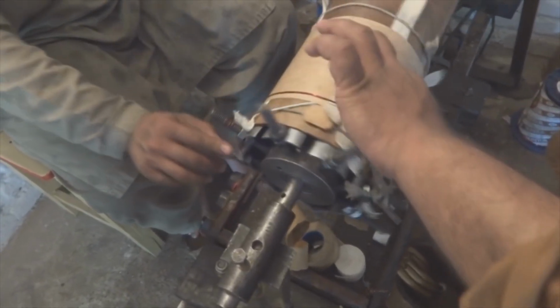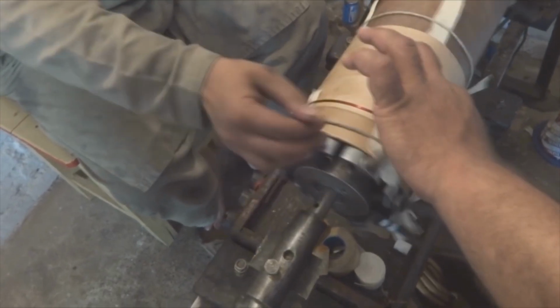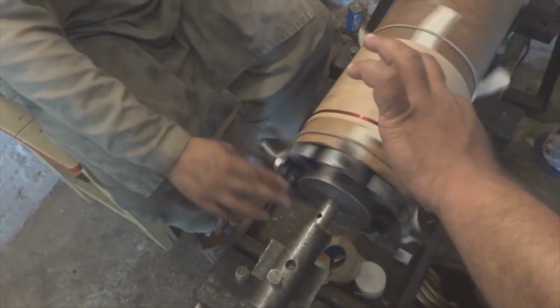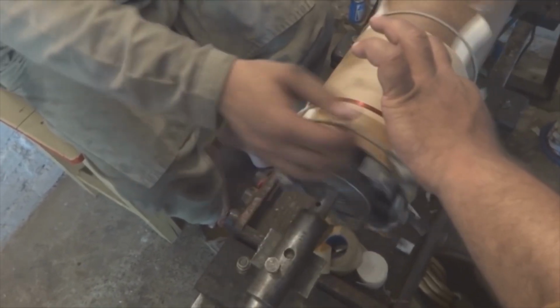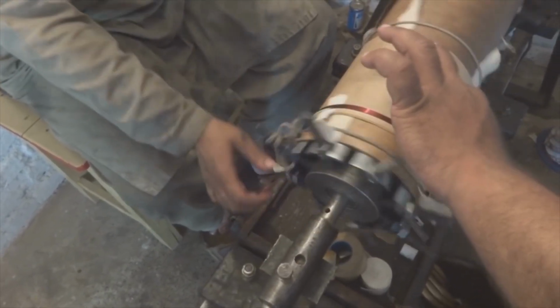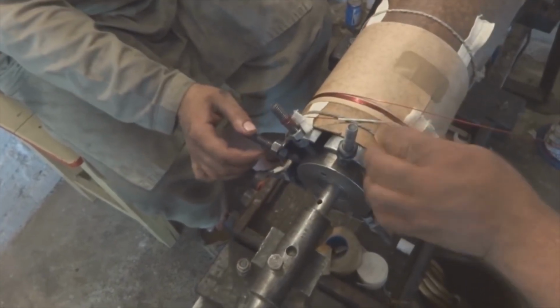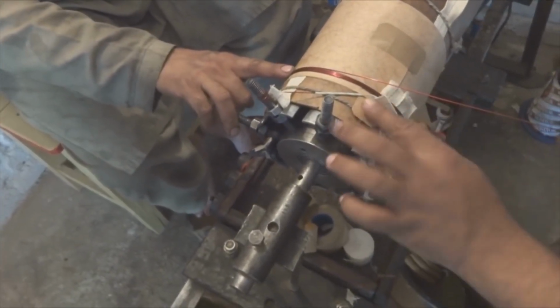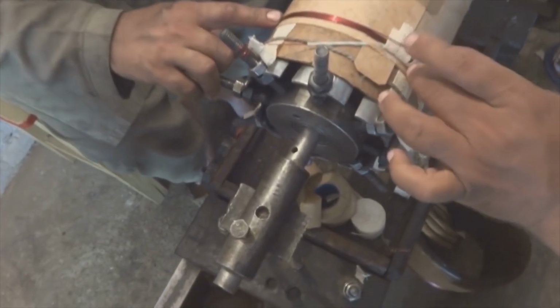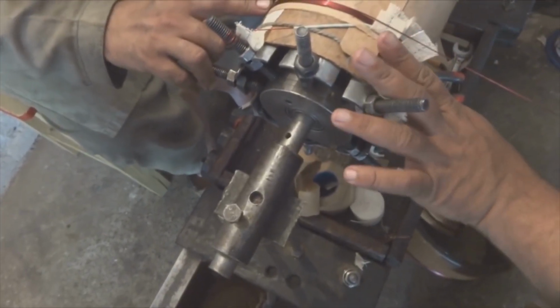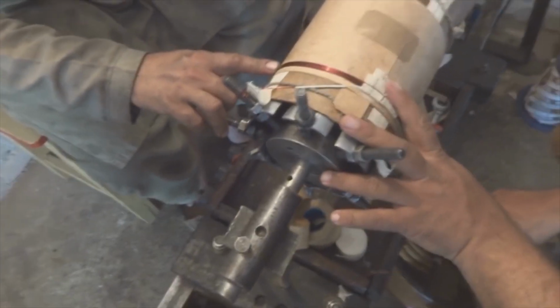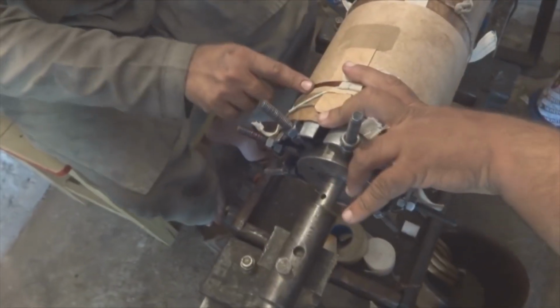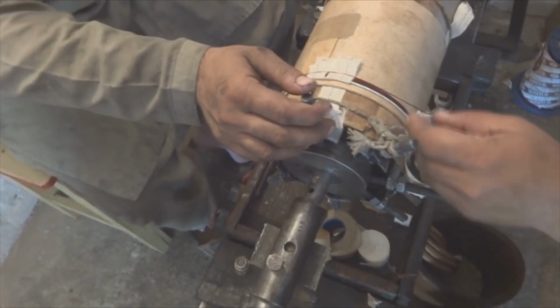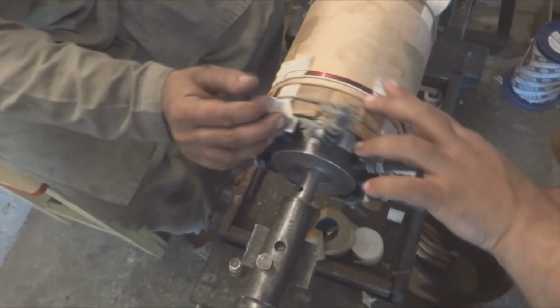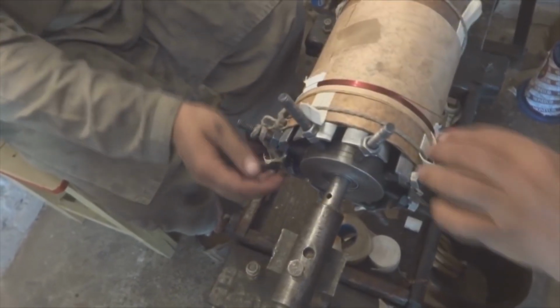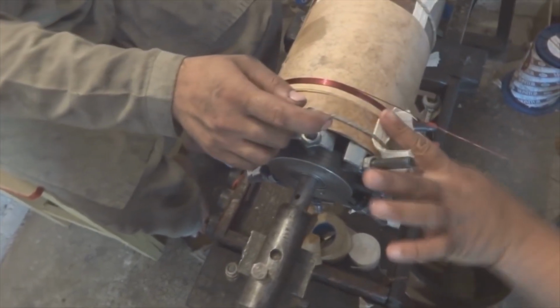So they just start by hand on the winding machine, putting in the first few turns by hand, and then later they start the motor machine. Now you can see they are just folding these tapes, and the next turns will follow on these folding tapes, so the previous turns will be held by the next turns. This is a very simple way to secure the windings and keep them tight, so they do not come off while the transformer is in function.